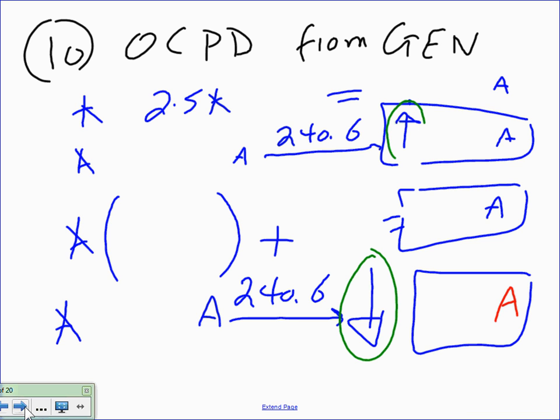First of all, you need to find the overcurrent protection device for the pump. So what we do is we take the full load amp of the pump multiplied by 2.5, because that's how we size the overcurrent protection device. If it was a motor by itself, then you take the 100 amp and size yourself based on 240.6, an actual physical mechanical size. They'll give you 100 amp, right? So first you find the overcurrent protection device for the pump by itself, assuming it's just a motor.